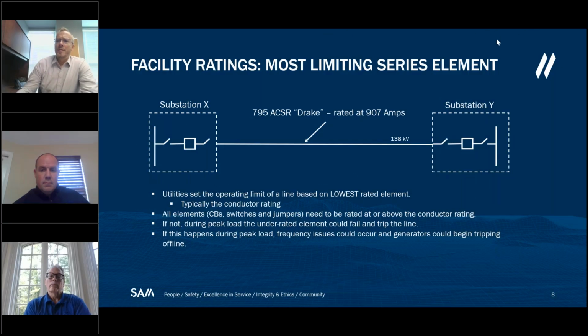So as I touched on, a facility rating is the current capabilities of a transmission line and the remote substations. In this example, we have a 138 kV line, 795 ACSR conductor rated at 907 amps. I think I pulled that off the Southwire conductor catalog. When you determine the facility rating, you need to consider the rating of the transmission line and the rating of the equipment inside substation X and substation Y.